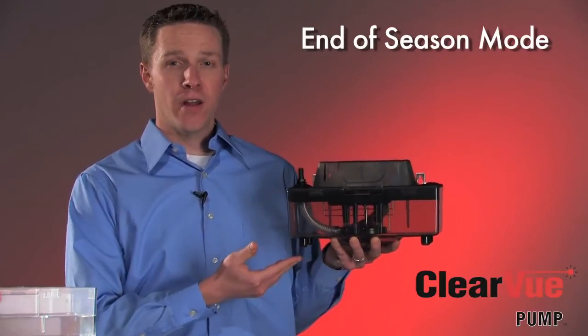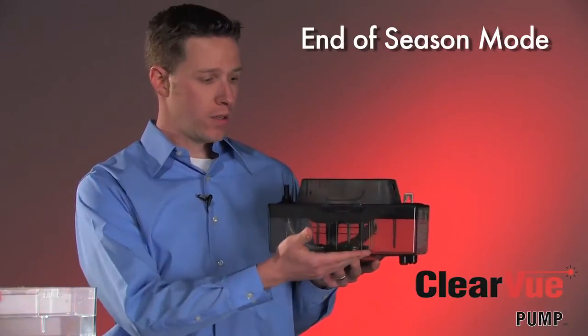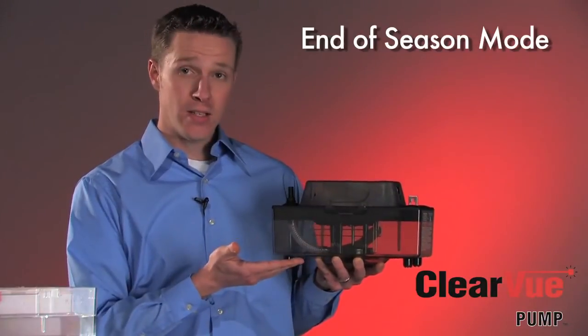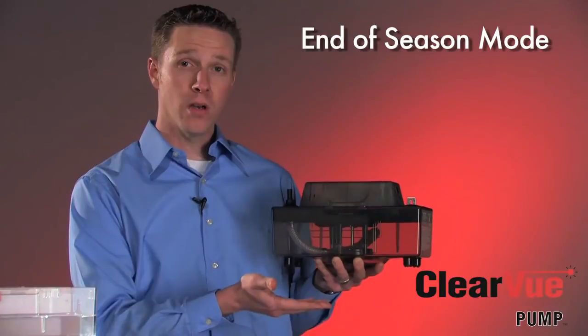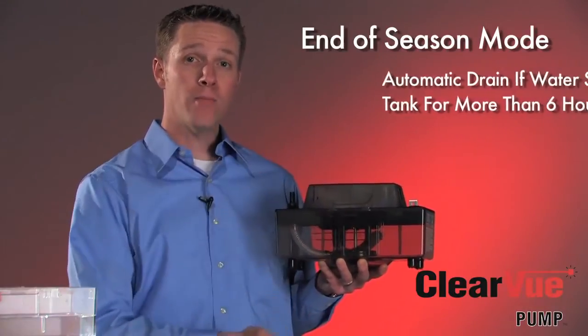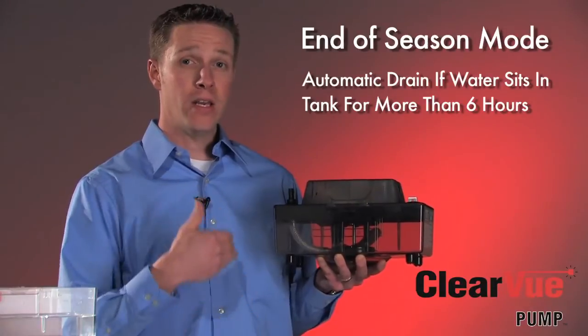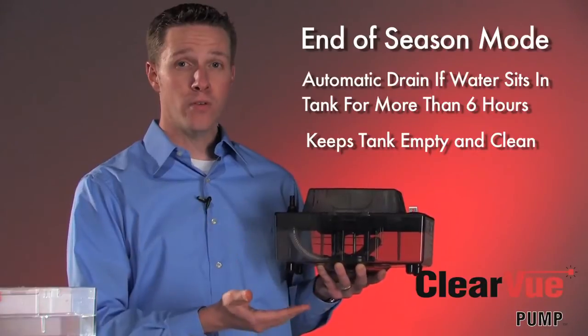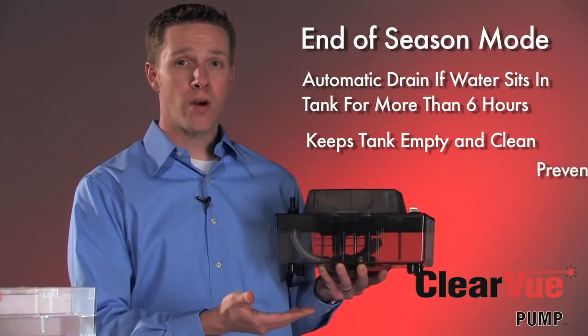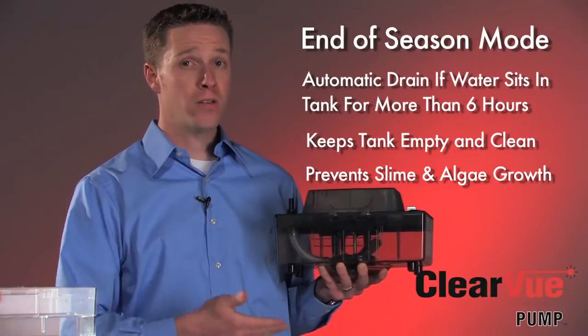The last feature I'd like to talk about with ClearVue is what we call our end of season mode. Basically, if water has remained in the tank for a period of six hours or more while touching the bottom sensor, ClearVue knows to run a pump-down cycle to get that water out of the tank to prevent any slime or algae buildup inside the tank. With ClearVue, it's almost 100% dry all the time, especially between seasons or periods of not cooling.